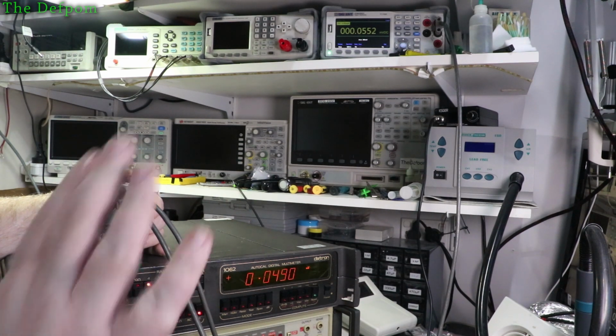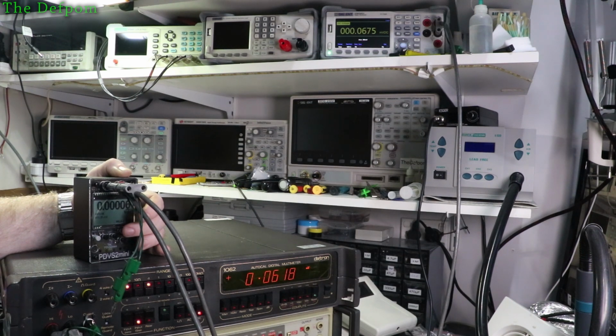So they are slightly apart there, but you're talking about minuscule numbers here. It depends on the linearity of the ADCs in both devices and stuff like that. So at this kind of level, it's just hard to measure - measuring microvolts, don't forget. So that's 90 microvolts there, and there's 7 microvolts difference between the two. And back to 100 microvolts.